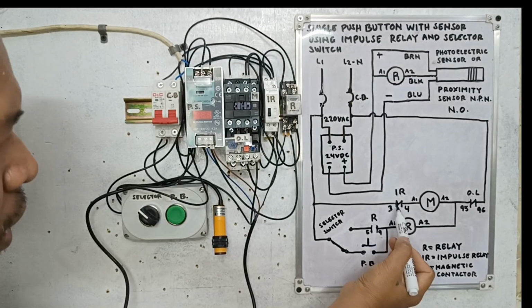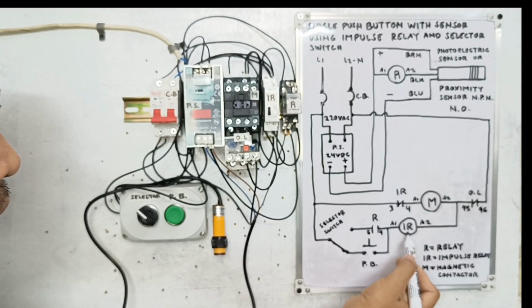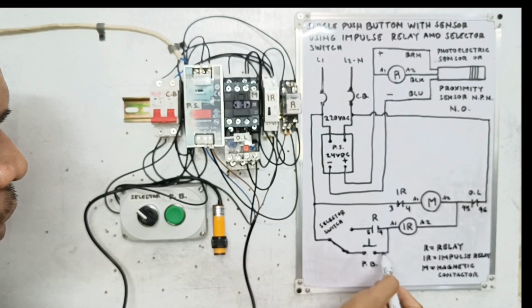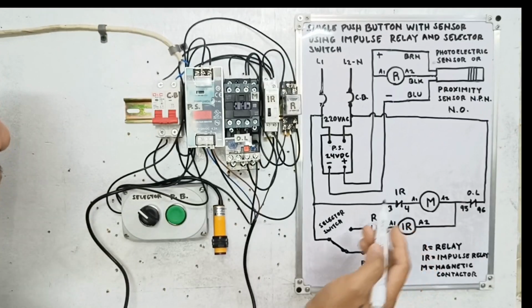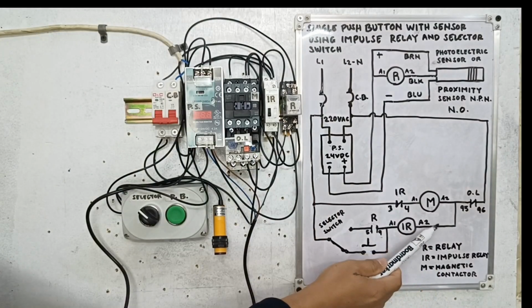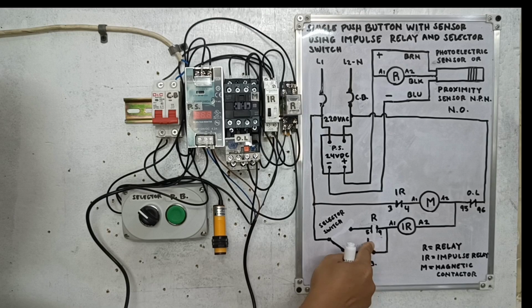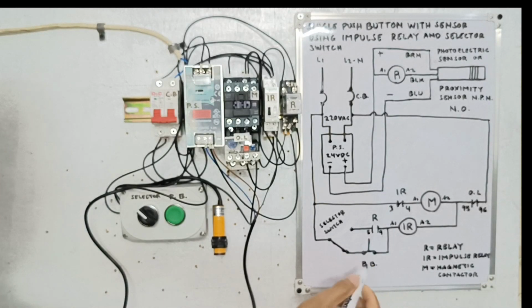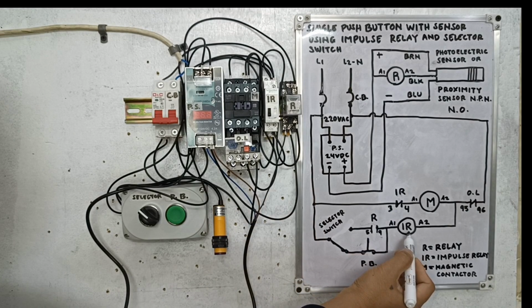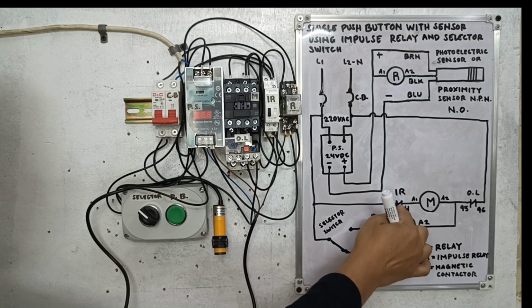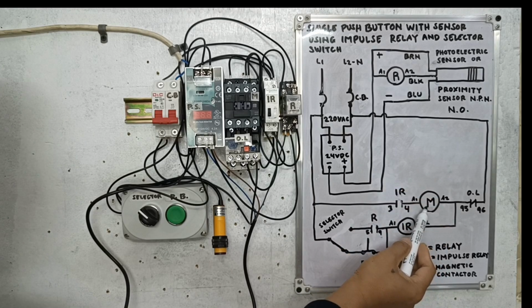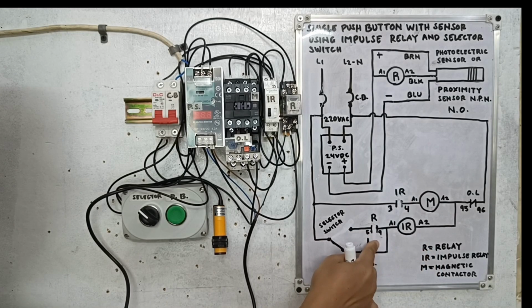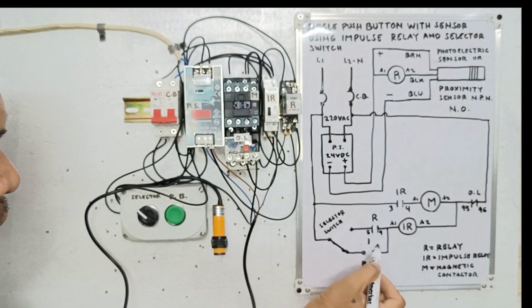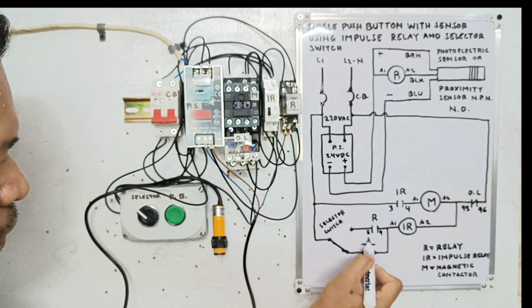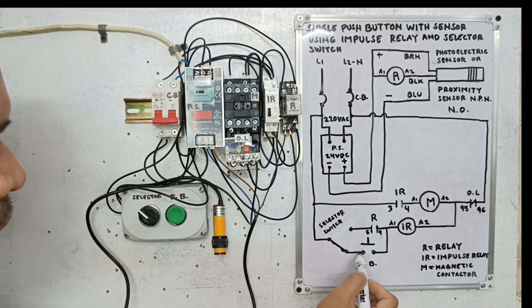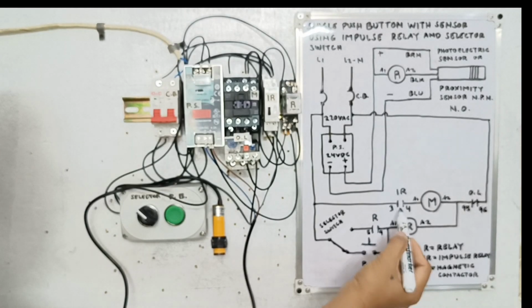So now this one will close. The impulse relay now will cut off the power because the power is only until here. But it's still closed because the impulse relay is reset for automatic. The magnetic contactor is still activated. Now, if we press this again, this one will close again. The current passes here and activates the impulse relay again. After the impulse relay activates, this one will open for the impulse relay. Now the magnetic contactor is off because the current is only until here. If we release this button, guys, it goes back to the normal open position, just like that. Now the current is only until here, the impulse relay will cut off the power, and this one will open.